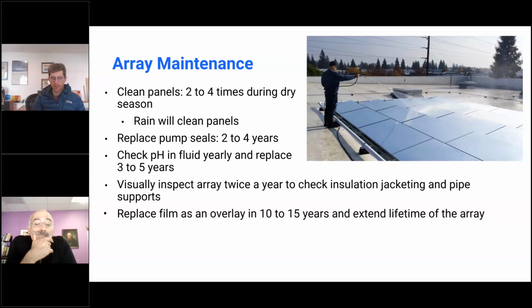There's visually inspecting the array. This is out on a roof. There's always things happening on a roof that you may not expect. But making sure that pipe insulation is still on the pipes, that's important as well. And then, that 10 to 15 year lifetime of the film, it makes sense to replace the film if you have a cooling system that's going to continue in operation beyond it, and you want to continue to use this as an asset. But if you don't replace the film, the reflectance of the film will start to decrease, which means the performance during the middle of the day and in the summer will go down, but the performance at night will be the same, and especially in the shoulder seasons when it's not as sunny outside.